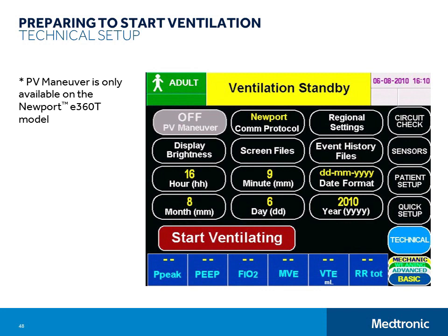Use the Communication Protocol button to select the RS-232 communication protocol that corresponds with the monitoring system that is connected to the E360 ventilator. Touch the button to select Newport, Newport 2, or View Link. Touch Regional Settings and then set altitude, language, and pressure units. Touch appropriate buttons for adjusting date format and date and time as needed.